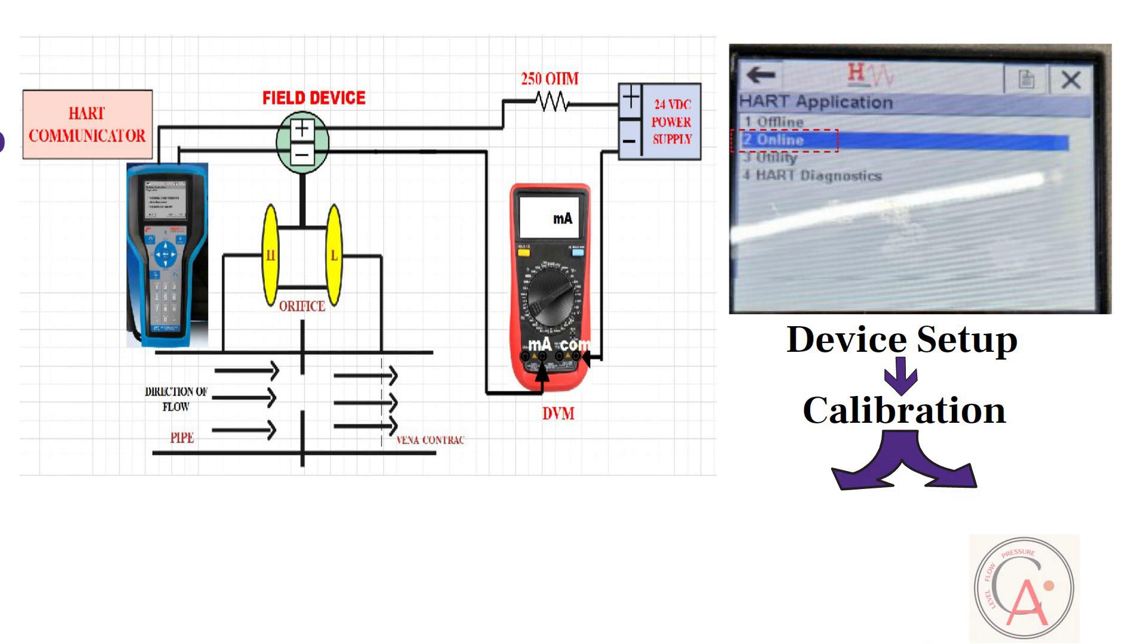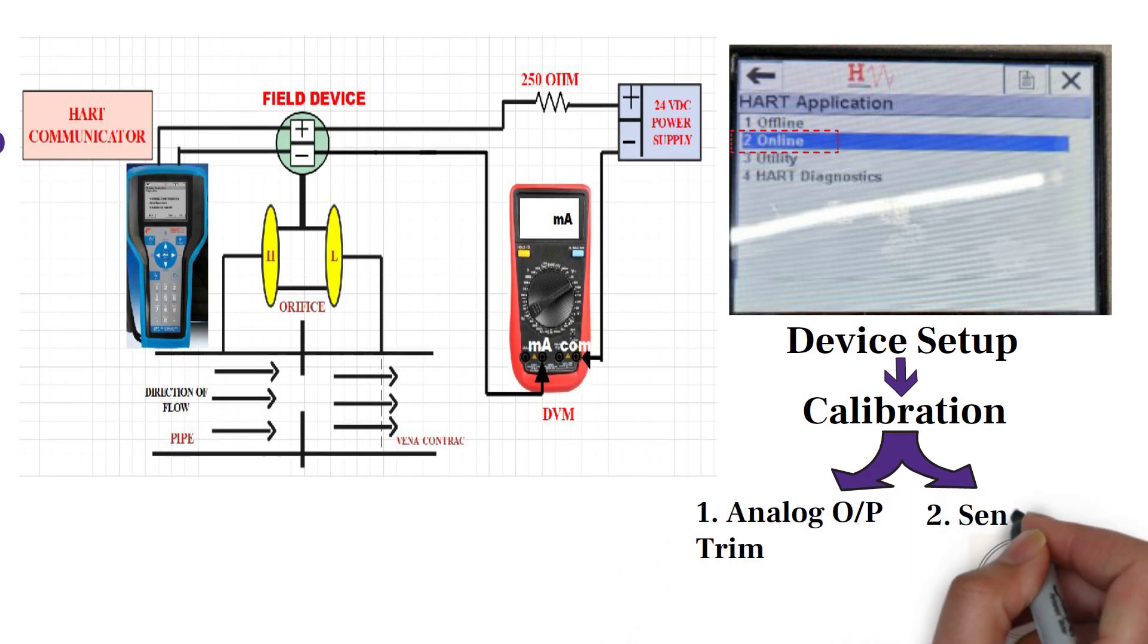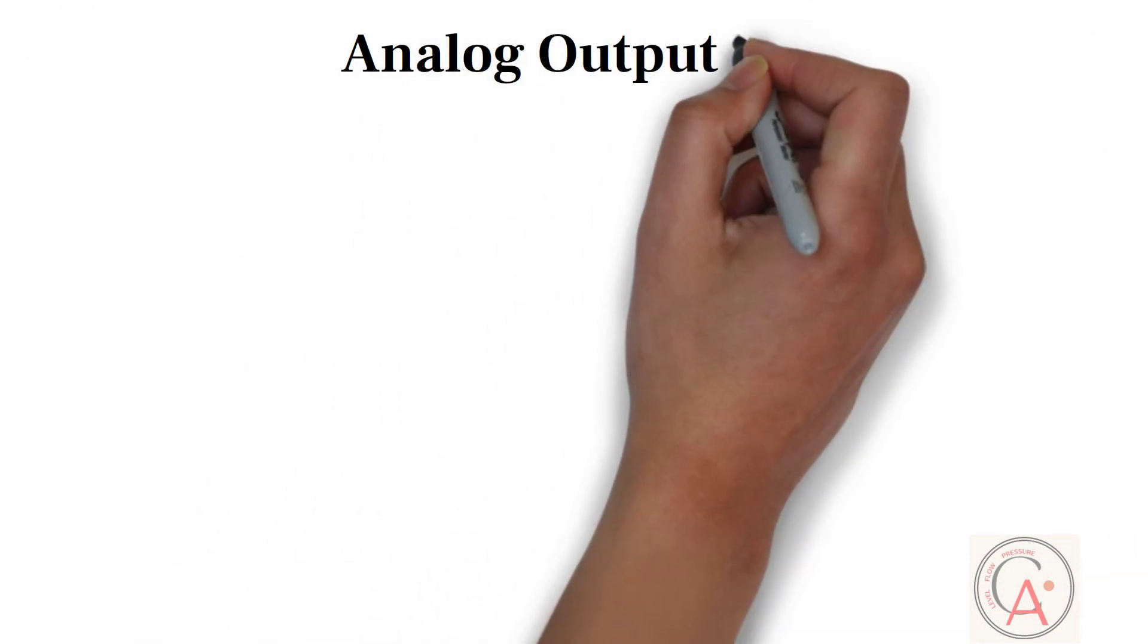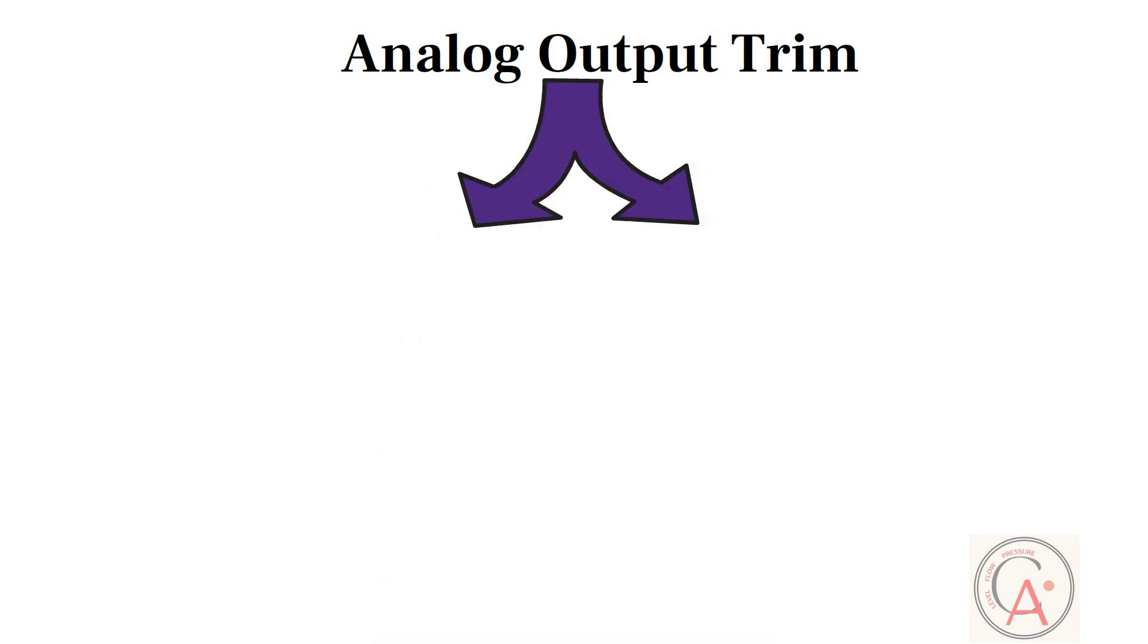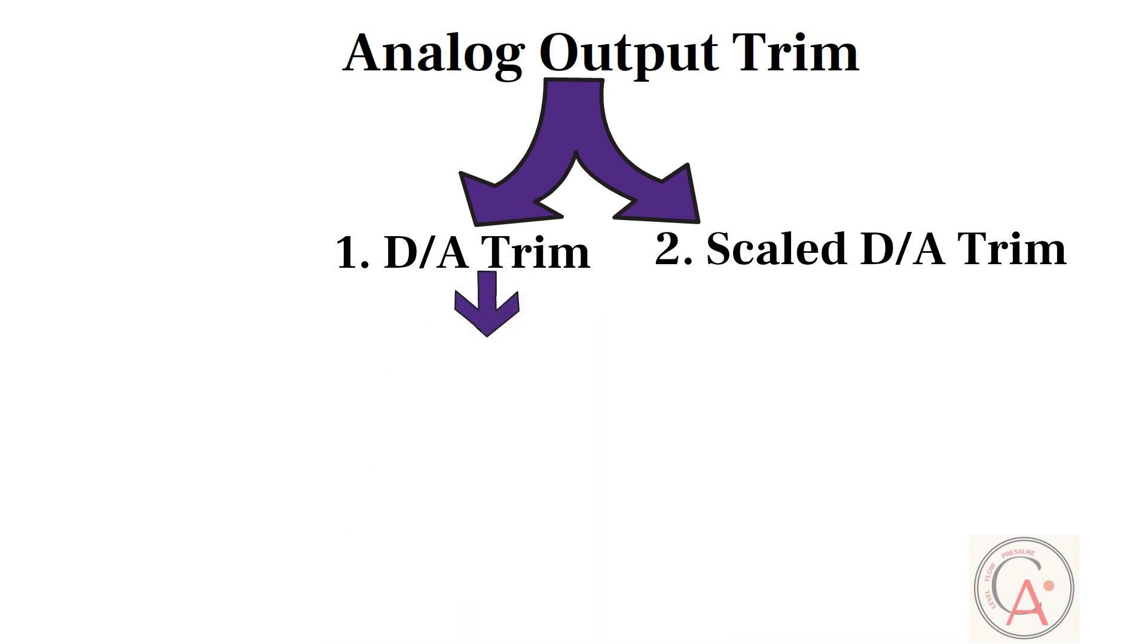Calibration menu has two options. First option is for analog output trim, and second option is for sensor trim. Select analog output trim option, and then select digital to analog trim option. At this time, connect reference meter message appears. Select OK and press ENTER button.